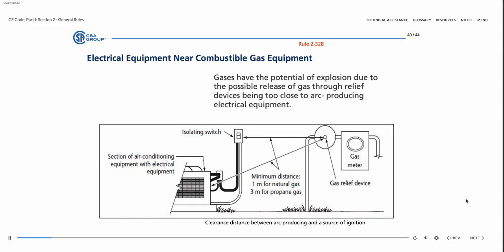Gases have the potential of explosion due to the possible release of gas through relief devices being too close to arc-producing electrical equipment. The clearance distances specified in CSA B149.1 between arc-producing and a source of ignition and a combustible gas relief discharge device, or vent, are as follows: 1 meter for natural gas and 3 meters for propane gas.